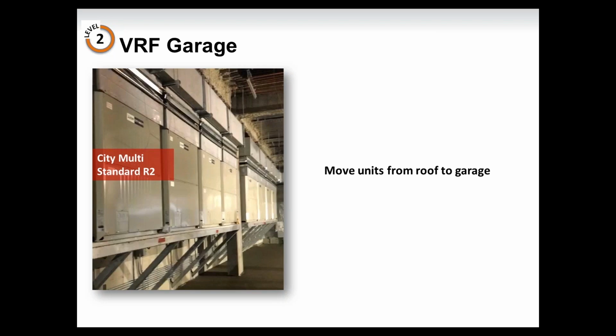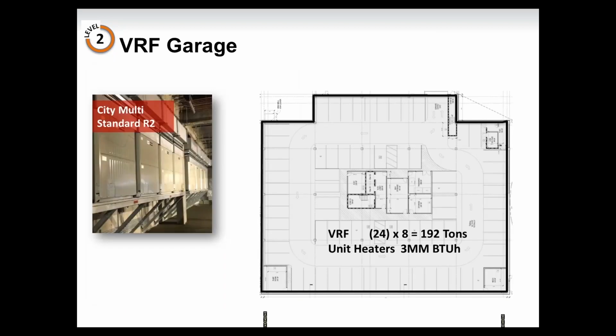This slide actually shows a picture of a system done similarly, where we've got the outdoor units mounted along the outside wall, ductwork on top of them, and the ductwork is either recirculating the air back into the garage or exhausting the air out of the garage, depending on the season. To do that, we have the same number of units, but we have to add 3 million BTUs of unit heaters for supplemental heat. So we show the units on both sides and then the unit heaters there.